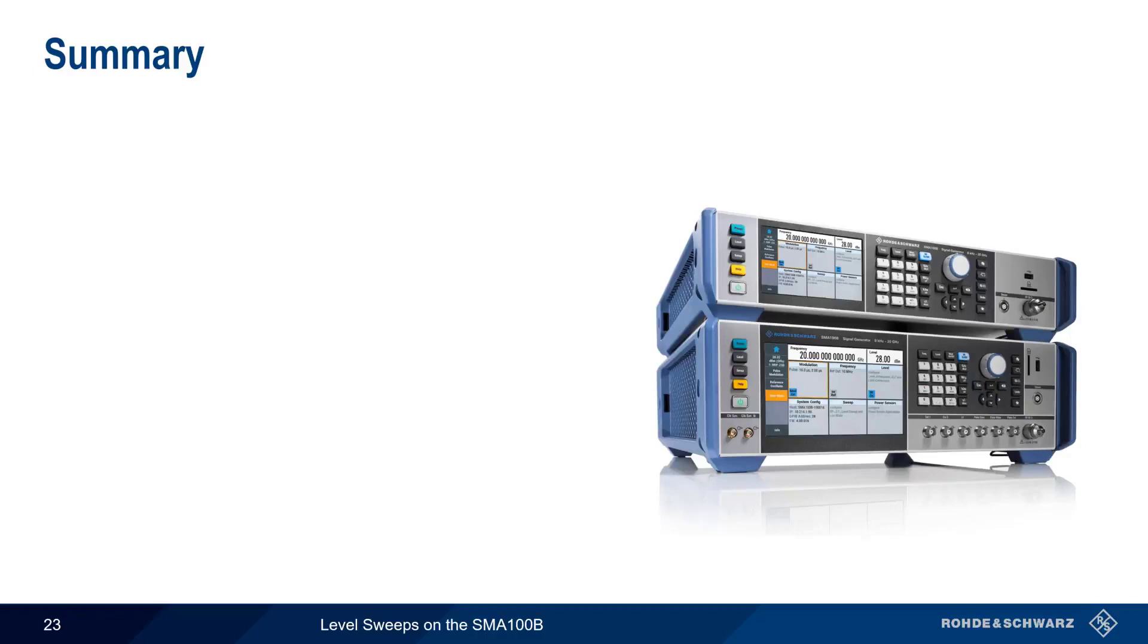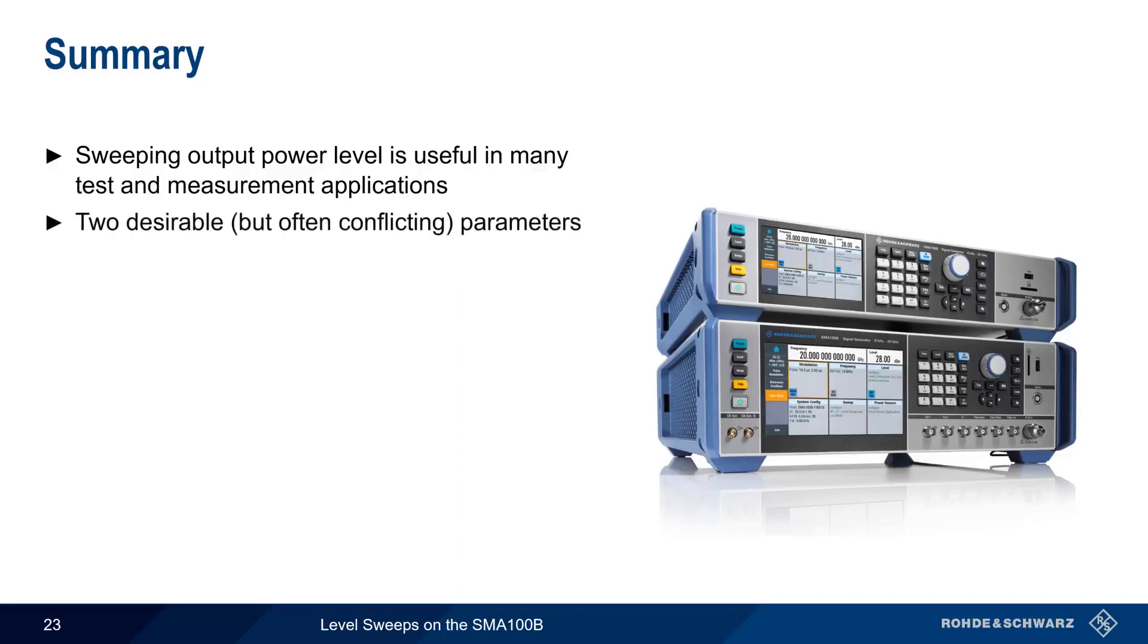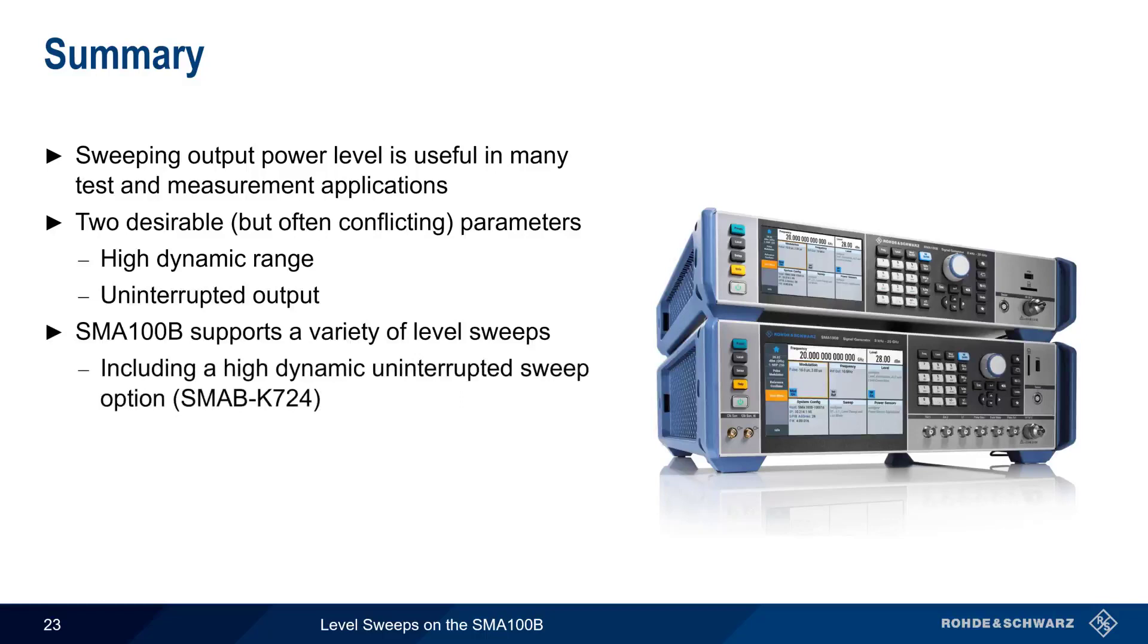Let's end with a brief summary. Sweeping the output power level of a signal generator is useful in many different test and measurement applications, for example in amplifier testing. Sweeps are relatively easy to configure, and there are two important sweep parameters, namely High Dynamic Range and Uninterrupted Output. In traditional signal generators, these were often conflicting parameters, with High Dynamic Range requiring blanking at different output levels. The SMA100B supports a variety of different level sweep types, including a High Dynamic Range Uninterrupted sweep, which allows wide output ranges without blanking.